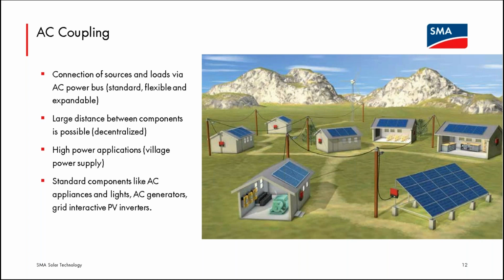There is a device called the multi-cluster box that can take multiple groups of Sunny Islands. And for the US device, it's multiple groups of 3 Sunny Islands. So it's a 3-phase device, and it can take power from 1, 2, 3, or 4 clusters of Sunny Islands and provide that synchronized to one loads panel. But that is really needed if you have more than 17,000 watts of load that must be driven to the same load and cannot be subdivided. Otherwise, it's much more direct to simply segregate the loads into separate loads panels that each have their own cluster of Sunny Islands, and the multi-cluster box is not required.